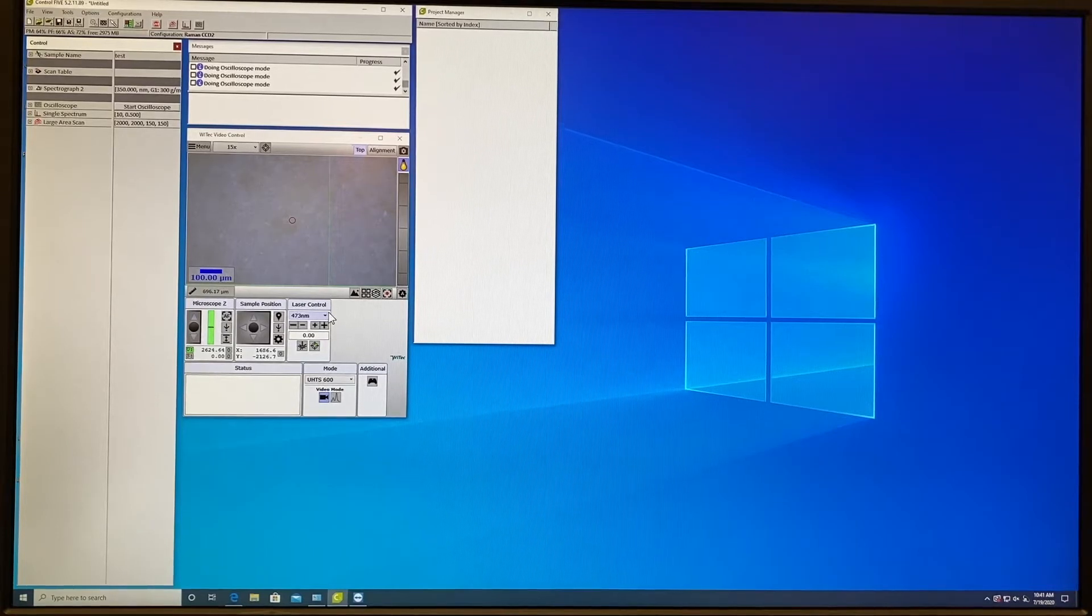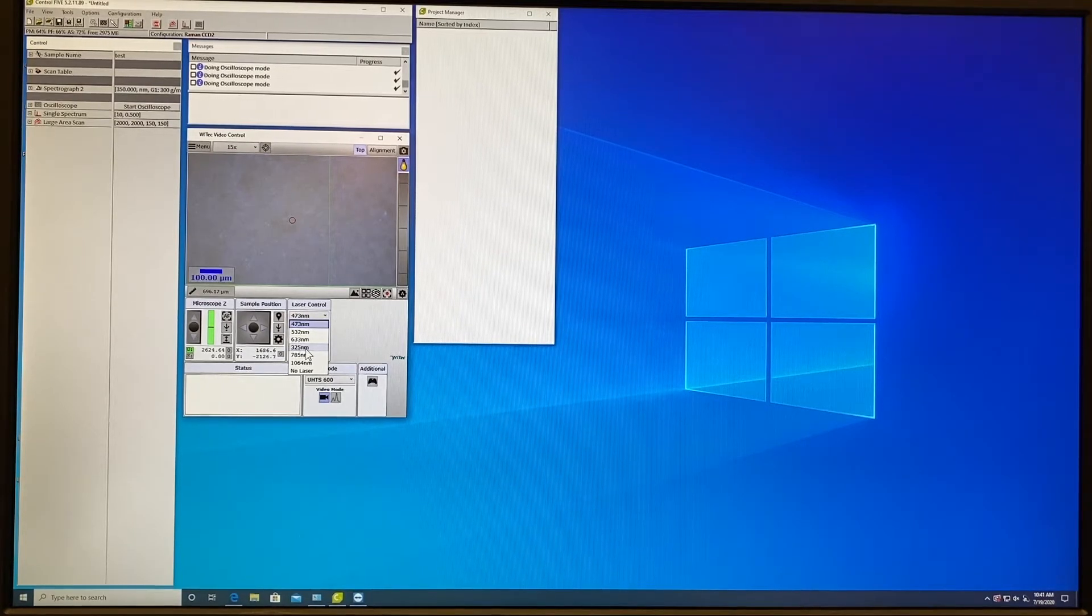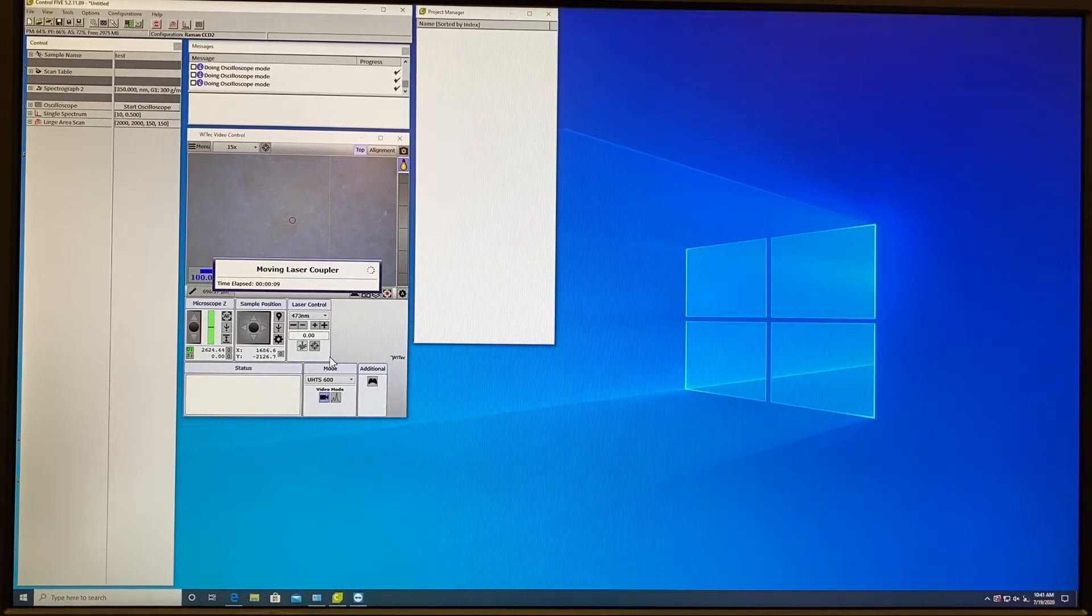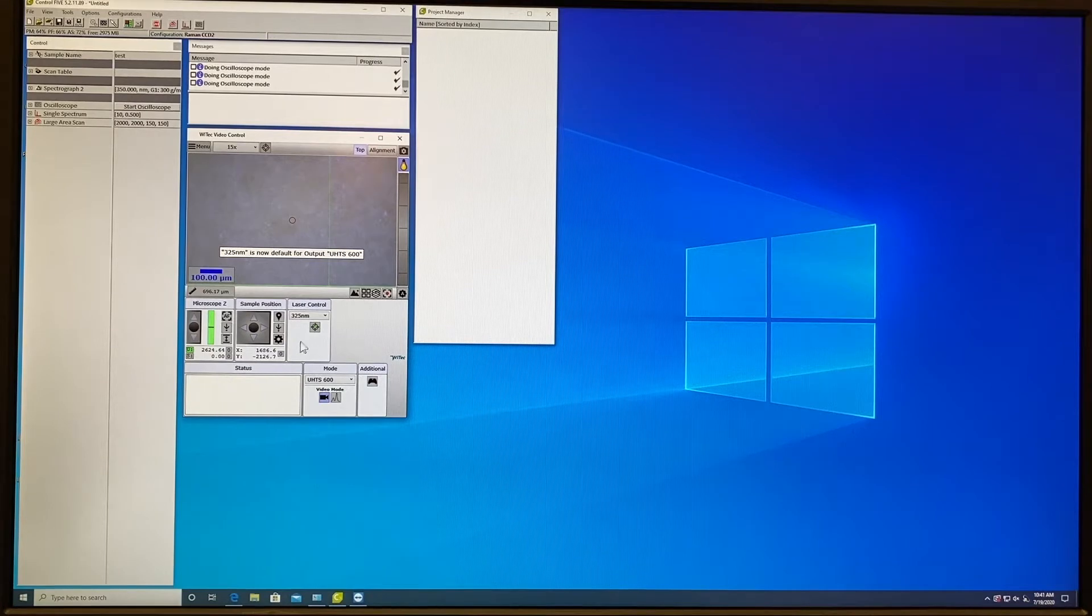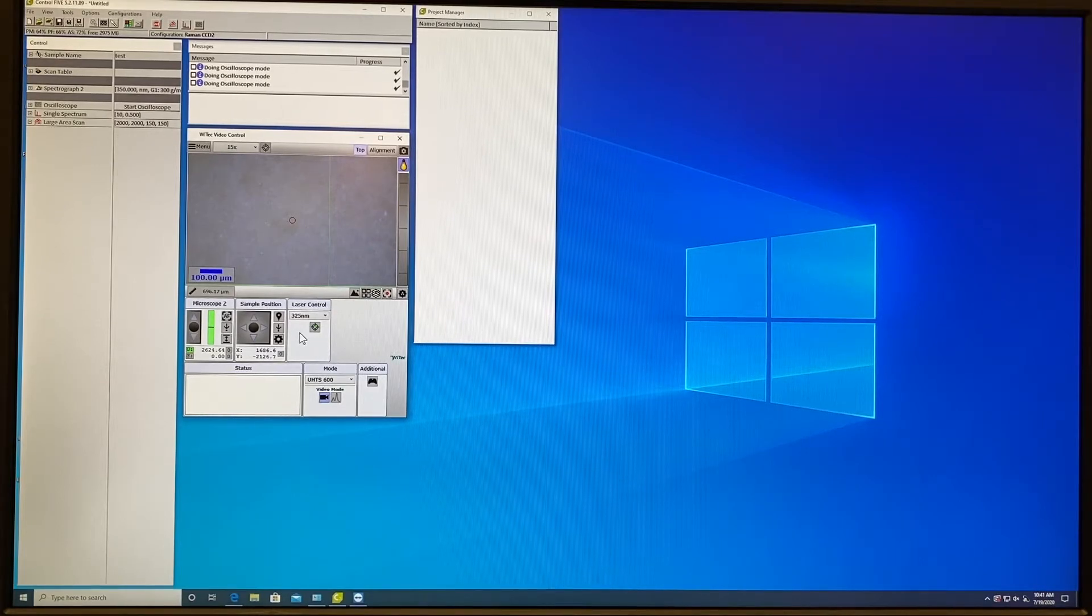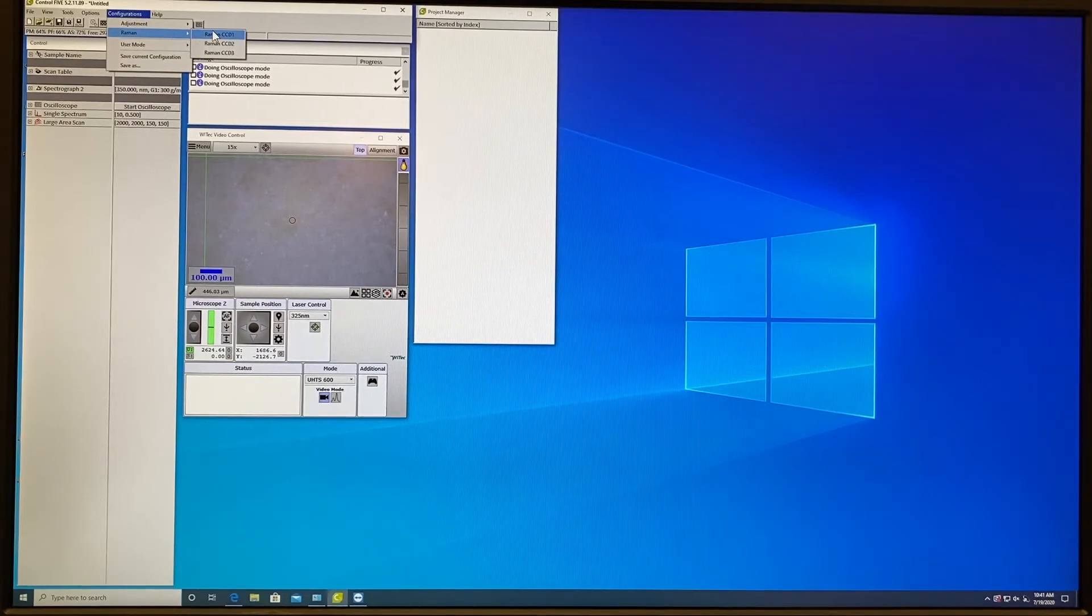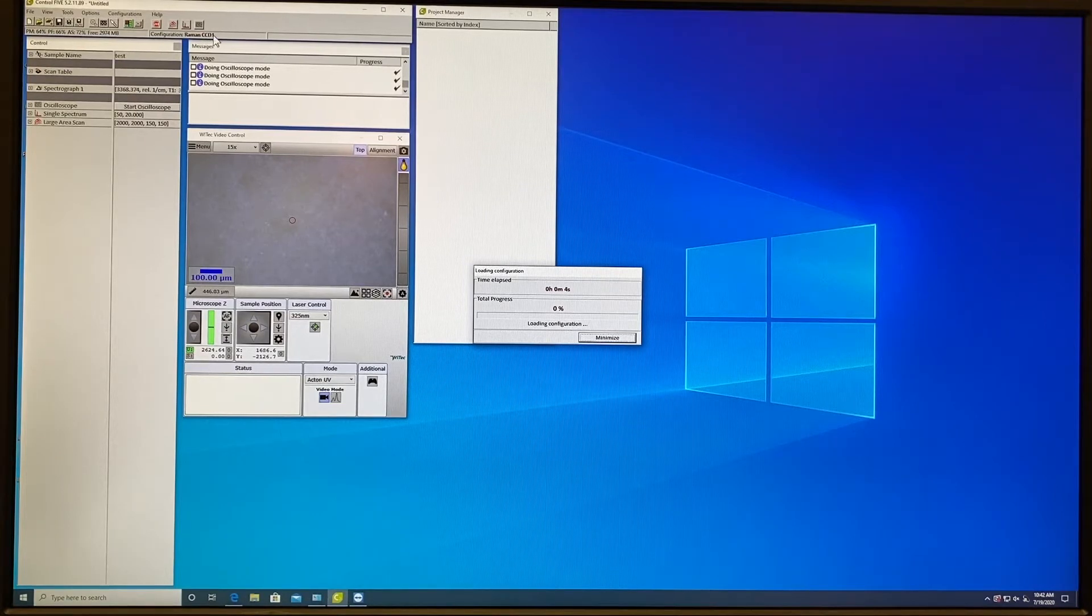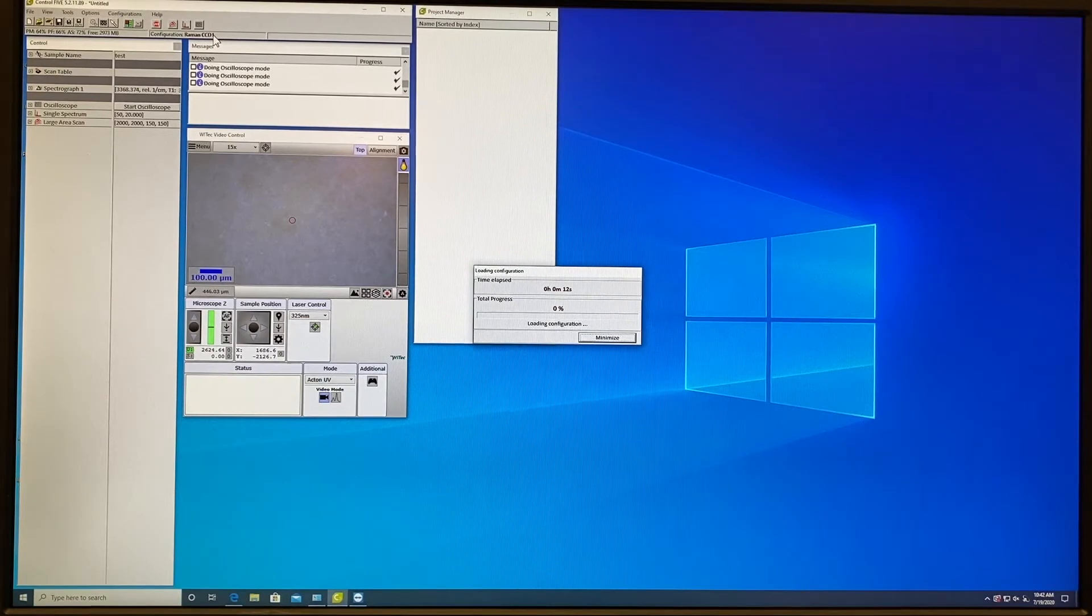Then you have to select the laser, 325 from this laser control window. So we use 325 nanometer laser, this is UV laser. You have to wait until the laser is adjusting and be patient for this, it takes some time. You will see that there is no window for the power adjustment as this is manually adjustable laser. Later I will show you how to operate. Then on the program you have to go to configuration, then Raman and choose CCD1 for UV laser. Click on Raman CCD1. Make sure that configuration is changed to Raman CCD1. Please be patient and wait until the program finishes adjustment.